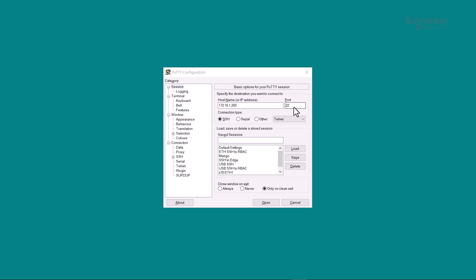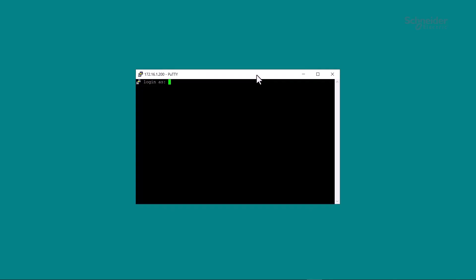To log in when using a terminal app, such as PuTTY, you need to configure an SSH connection. The port number is 2222 and the IP address is either 10.2.3.4 for a USB connection or the configured IP address of the LAN port being used. If you use a serial port, the port needs to be configured for command line mode and the serial parameters need to match.